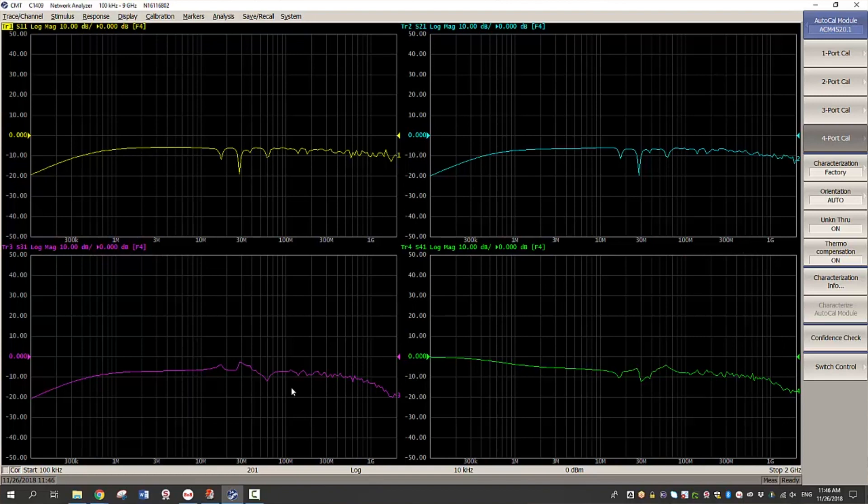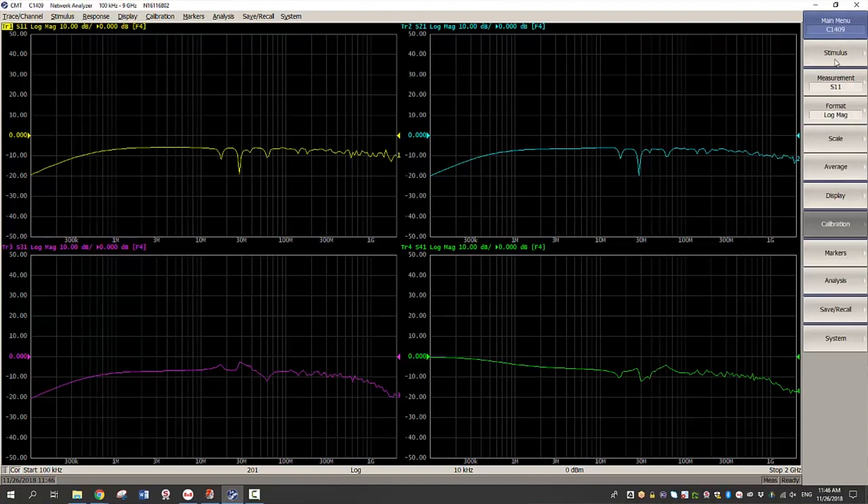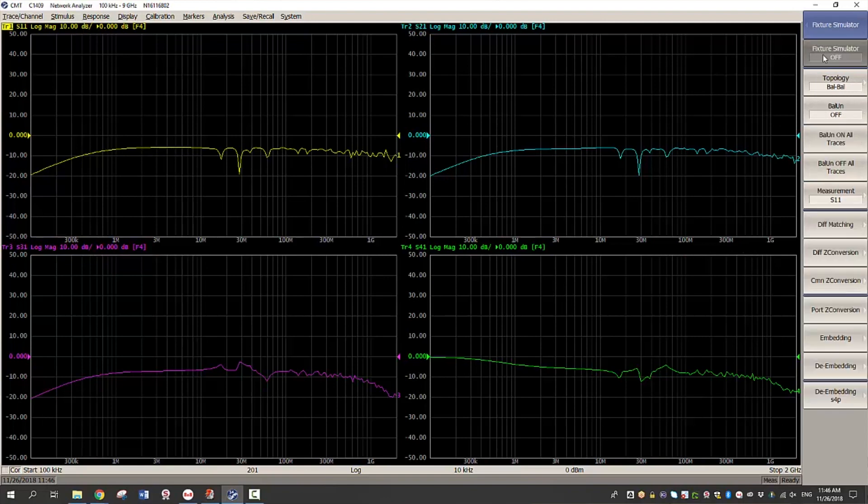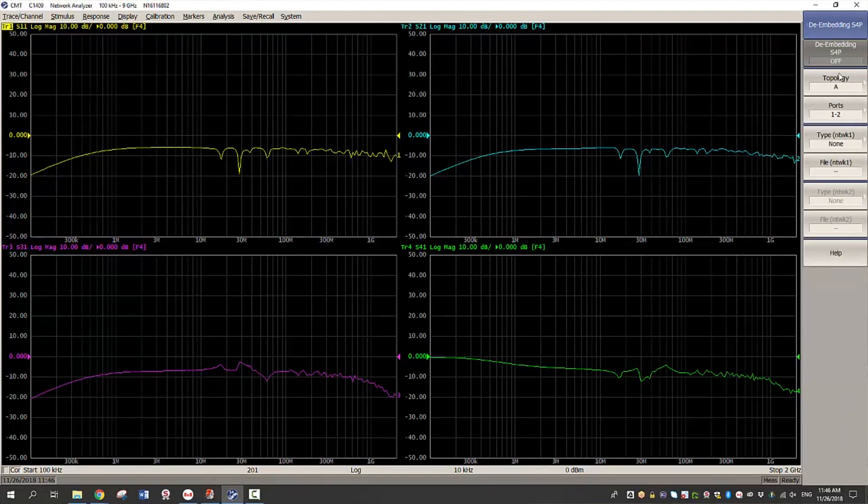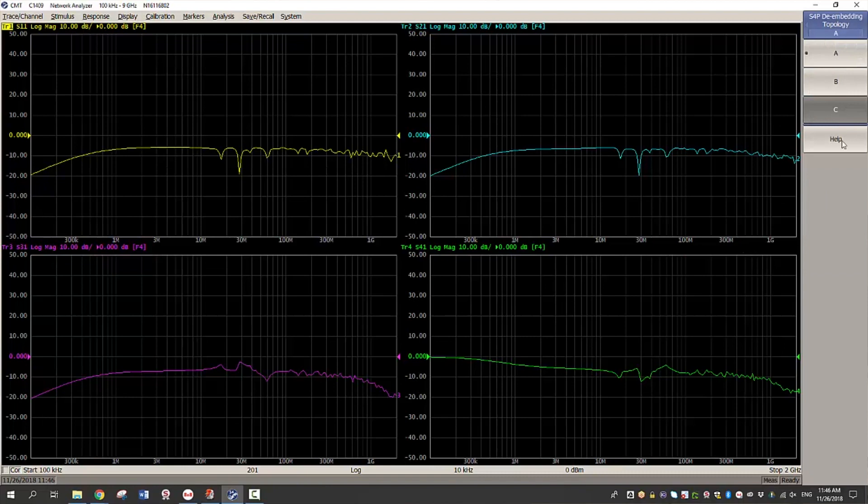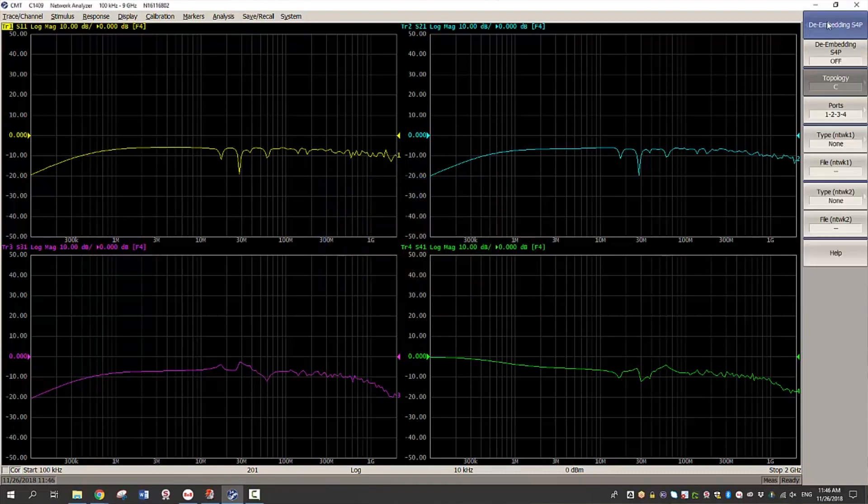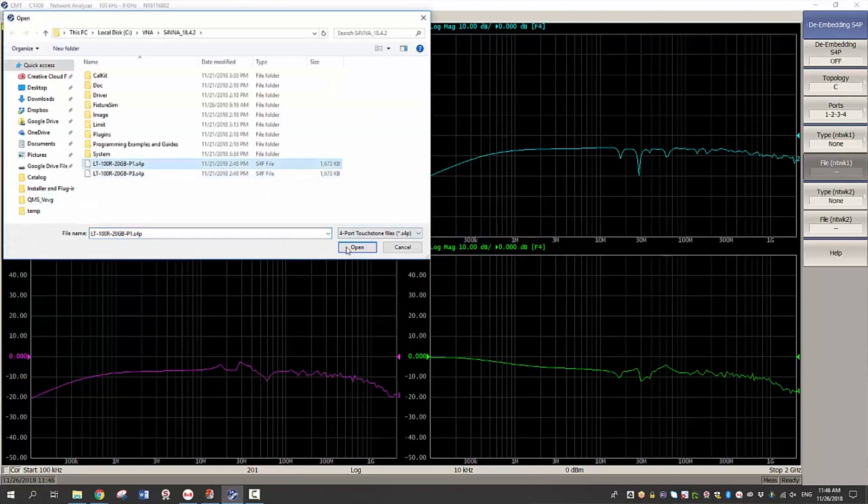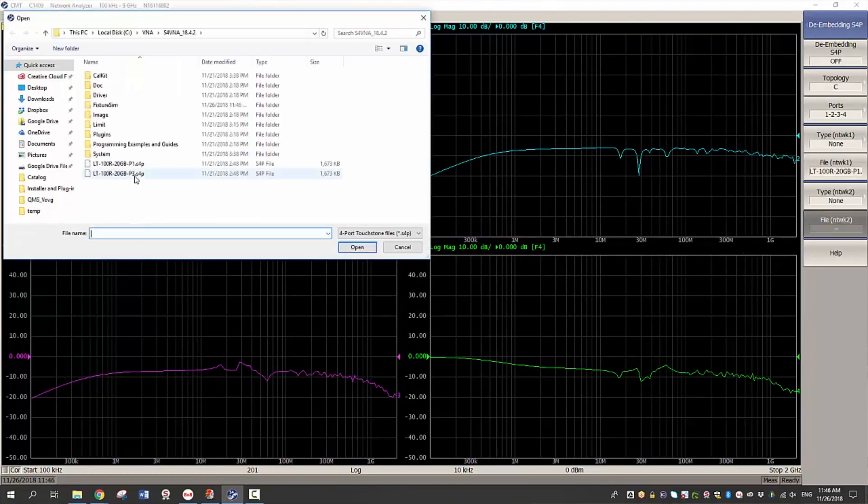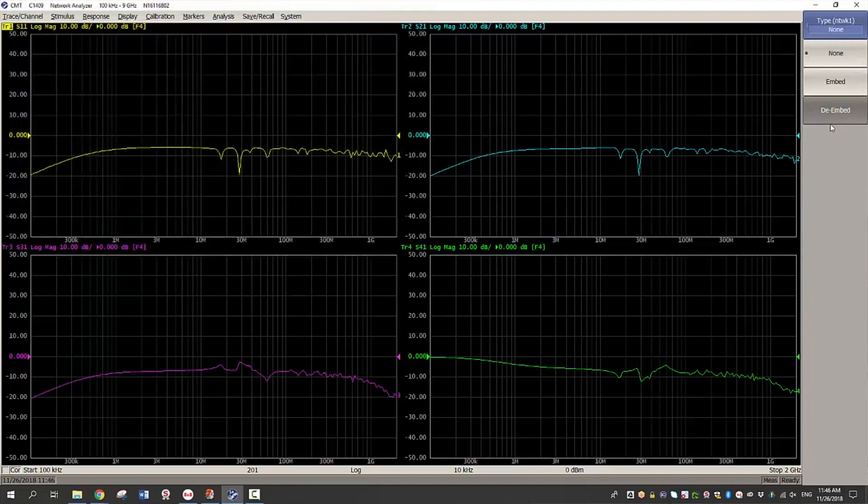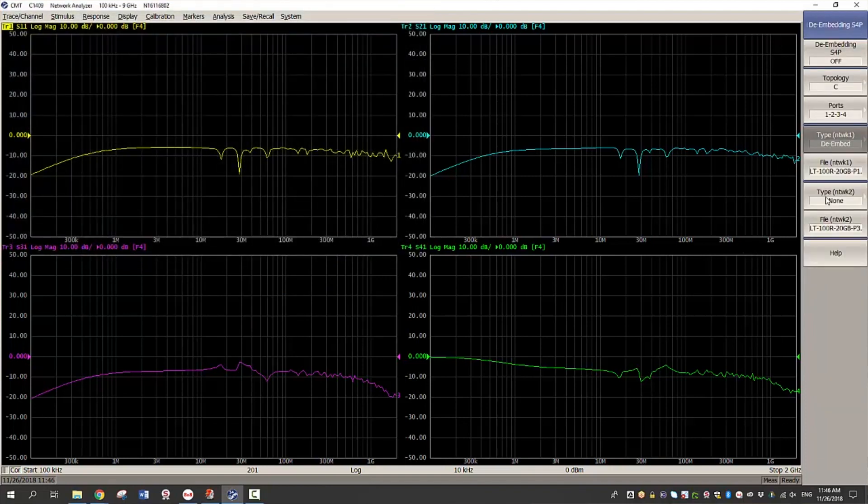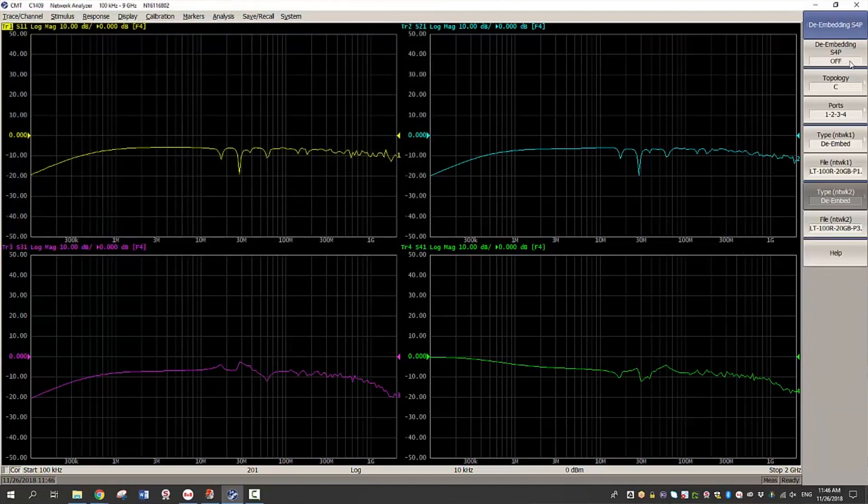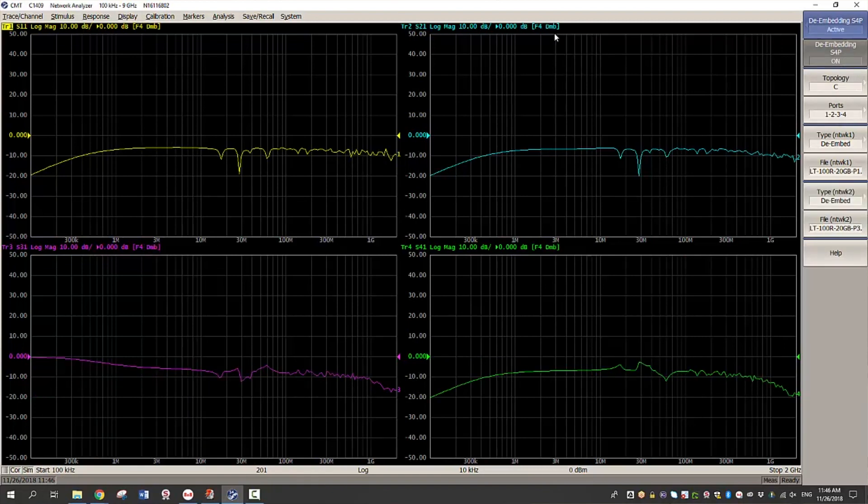So next step is to connect the fixture and then de-embed it. Go to analysis, fixture simulator, de-embedding, select the appropriate topology. So topology C is more suitable here and then choose the file and then de-embed both the networks and then finally turn on. Here DMB indicates that the de-embedding has been applied.